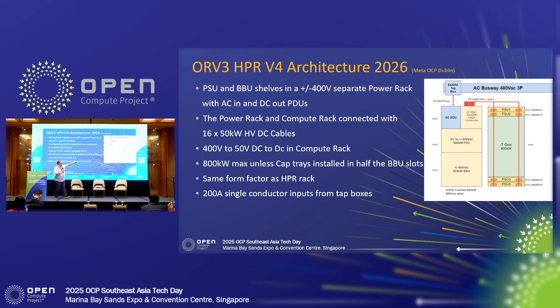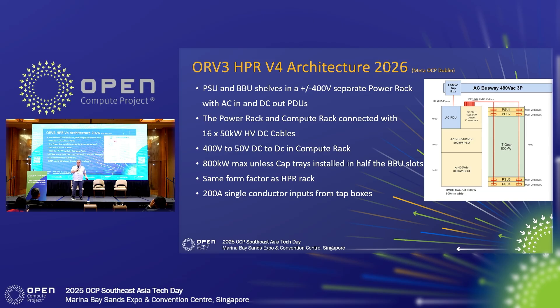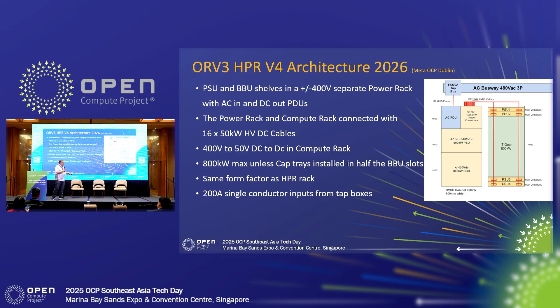Then we go to plus-or-minus 400 volts between the power rack and the compute rack. The servers in the compute rack all run on 50 volts, so if I bring in 400 volts I need a 400-to-50-volt DC-to-DC converter in the compute rack. What you'll also hear is that NVIDIA wants 800 volts, not plus-or-minus 400, because the reality is they wanted 800 volts all along. But you couldn't do it — there weren't enough components. So we'll run at 400 for a while, and once we have enough components we move to 800 volts, where an 800-to-50-volt DC-to-DC sits in the compute rack.